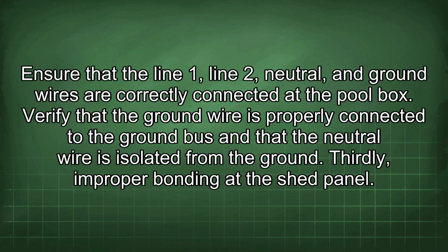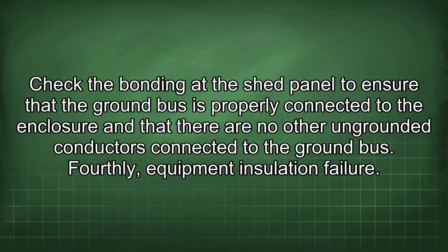Ensure that the line 1, line 2, neutral, and ground wires are correctly connected at the pull box. Verify that the ground wire is properly connected to the ground bus and that the neutral wire is isolated from the ground. Thirdly, improper bonding at the shed panel. Check the bonding at the shed panel to ensure that the ground bus is properly connected to the enclosure and that there are no other ungrounded conductors connected to the ground bus.